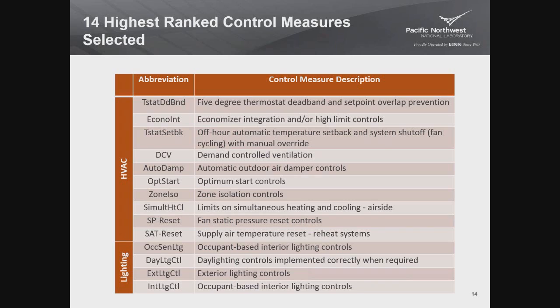Demand control ventilation. This is a requirement that applies to densely occupied spaces like conference rooms or gymnasiums. What this does is outdoor air needs to be brought into spaces to ventilate for people. And when you design a system, for example, a conference room, you have to make sure you have enough outside air for all the people that might be in there. You might have a conference room that holds 50 people, but very rarely are those 50 people all going to be in there. So demand control ventilation says when there's fewer occupants, you control the amount of outside air and reduce it so that you don't bring in as much and waste energy. That's typically controlled by a CO2 sensor.